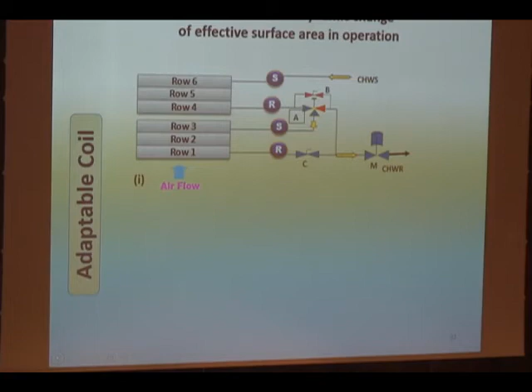It's changing the effective surface area of the coil to reduce in terms of what we need. So here we have just these 3 rows being effectively used. These 3 rows exist, but they are kind of static. There's dead water. Nothing is flowing through it. The manipulation of water flow is water goes through to 6, comes out at 4, and then it goes into the modulating valve here. So here is a strategy, very simple strategy that we can employ.